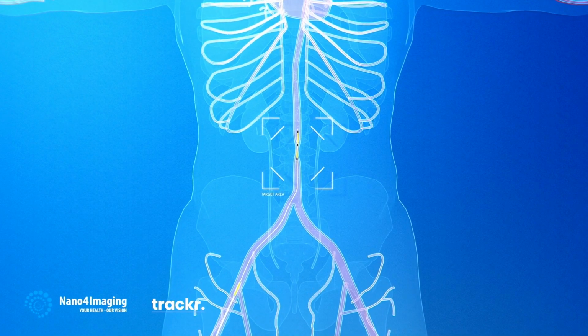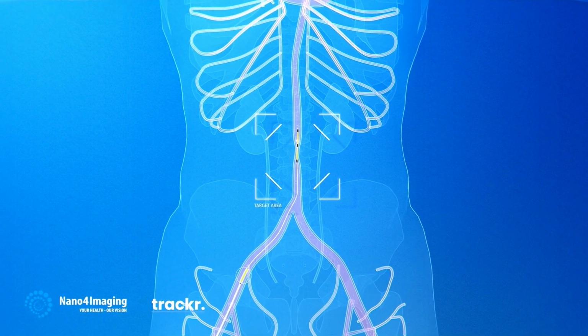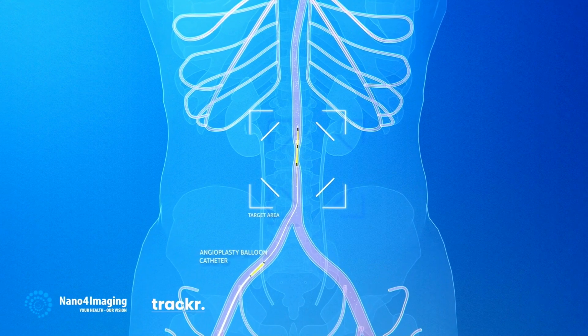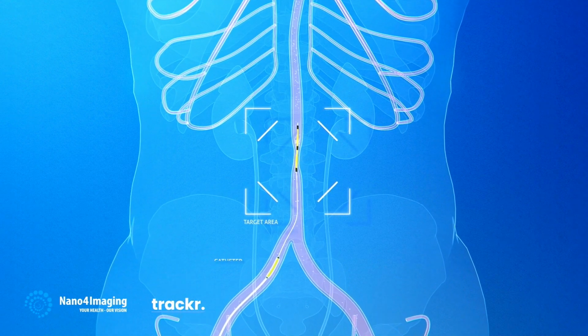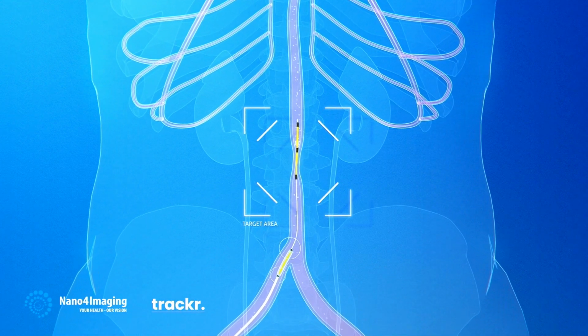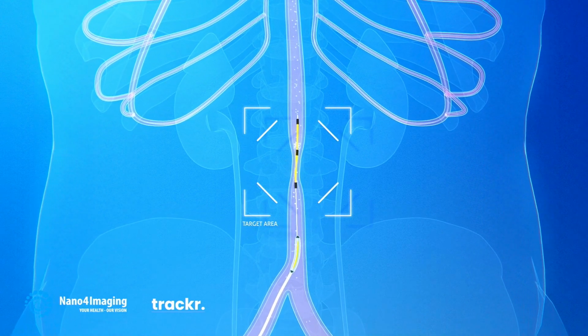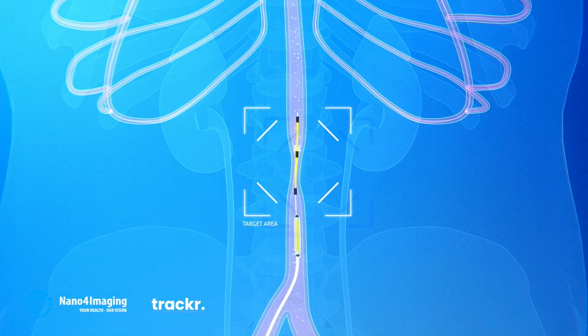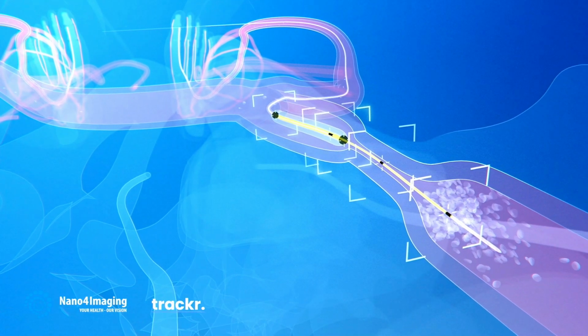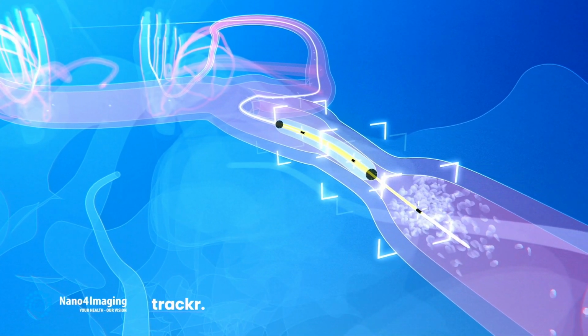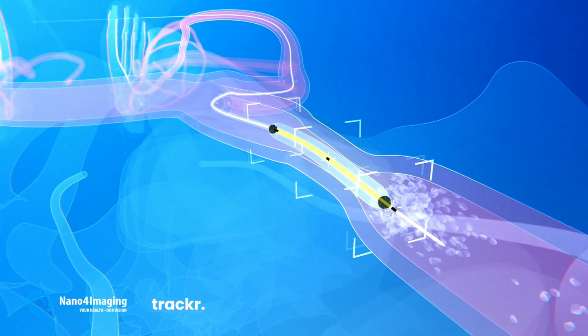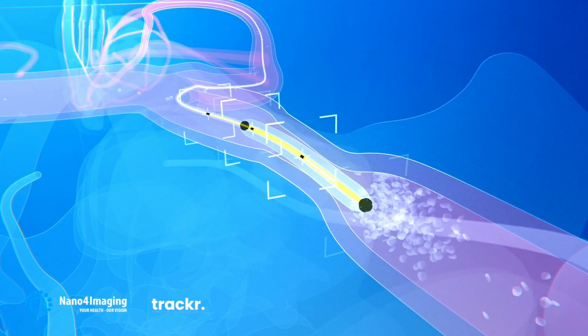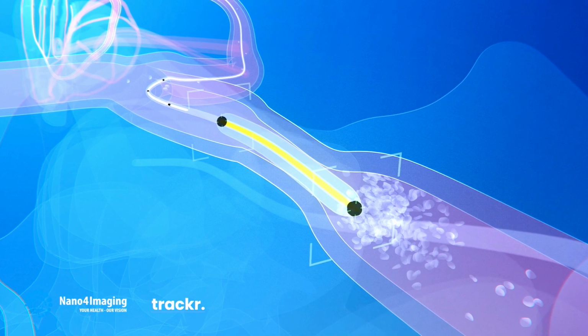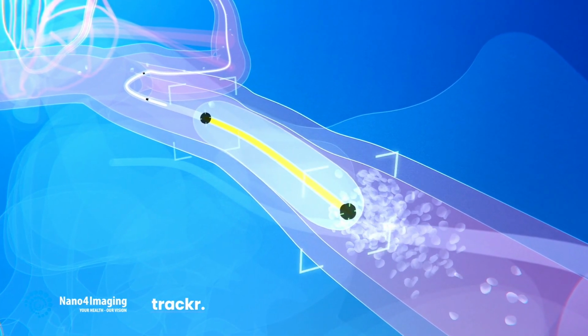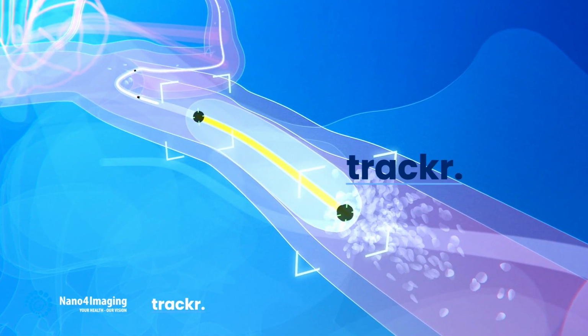Now that the wire is positioned in the target area, the angioplasty balloon catheter can be moved over the wire to the region of interest. It has 2 markers on each side and can be moved over the guide wire towards its distal position. In fact, the 2 balloon markers can be matched to the 3 markers of the guide wire pre-positioned in the stenotic area. The guide wire is then retrieved to allow balloon inflation. At all times, the markers on the tapered tips of the balloon remain visible.